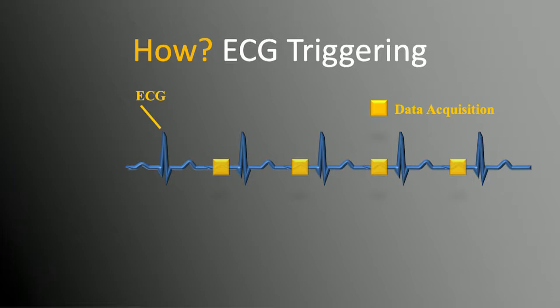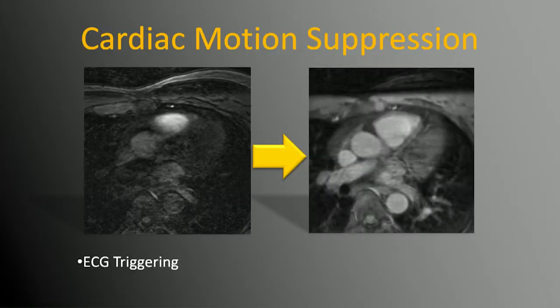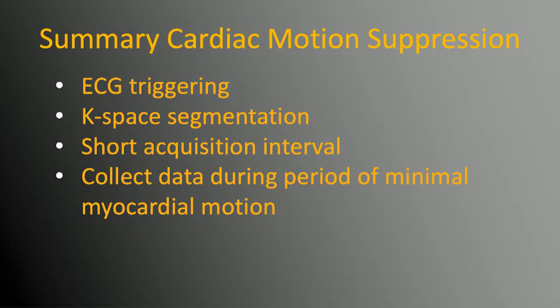You can see here in this slide, I always do this at the same time point in the cardiac cycle, where I'm thinking that the heart always has the same shape. So I keep collecting segment by segment of the heart. Of course, you have to think case-based. I simplified this here, but you see the concept. By adding up these pieces, which were always acquired at the same time point, I can now get to a coherent image. And if I now add EKG gating to the image on your left, you can see it already gets much sharper and certain details already become visible.